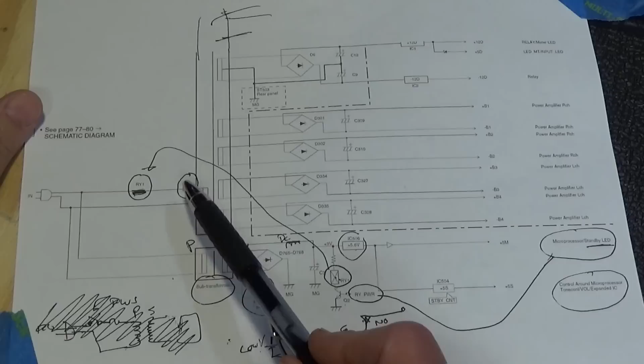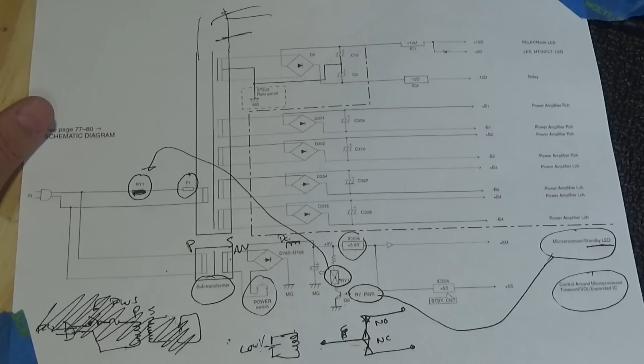Again, I expect to hear the relay regardless of whether that fuse is blown, and I certainly don't know how the microprocessor would detect a blown fuse and not turn the relay on. There's nothing in the circuitry that would do that. But we shall see.